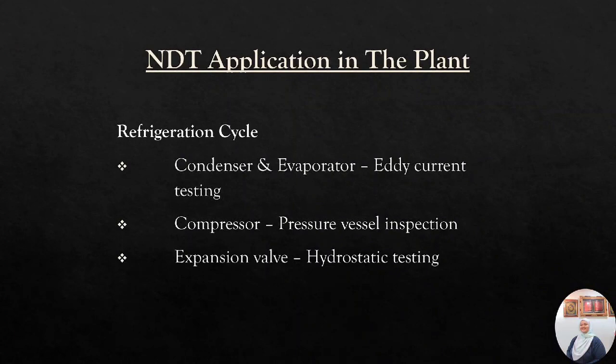Next is the compressor. The compressor will undergo pressure vessel inspection. The failure of a pressure vessel can result in the rapid release of a large amount of energy. To protect against this dangerous event, the tanks are inspected using radiography and ultrasonic testing. And lastly, the expansion valve will undergo hydrostatic testing.